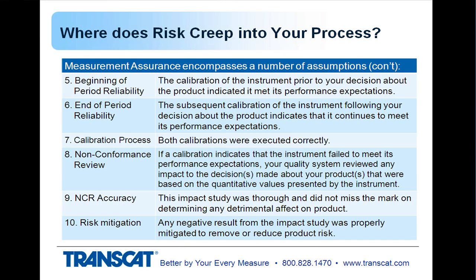A term that I call beginning of period reliability, and that is the calibration of the instrument prior to using it in your production process. Does it meet its performance expectations prior to you putting it into place? And then the end of period reliability is at the end of the calibration cycle, that subsequent calibration, and does it indicate that there was any error in the instrument when you were using it to make decisions about the process? And then the calibration process itself. Were those calibrations executed correctly? And I'll go into more detail of that in a few minutes.